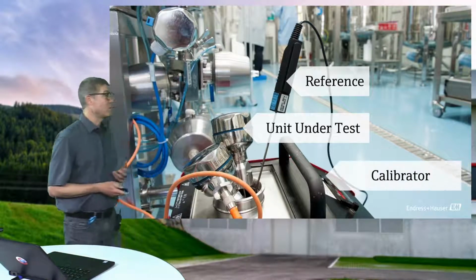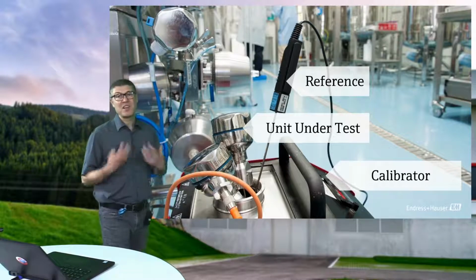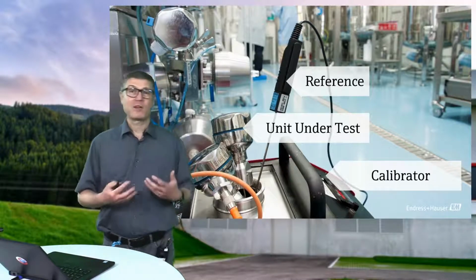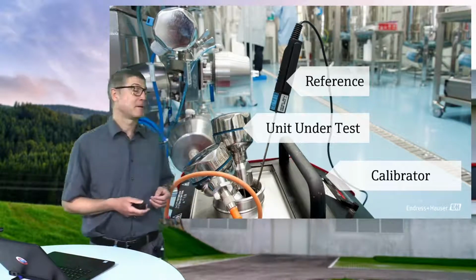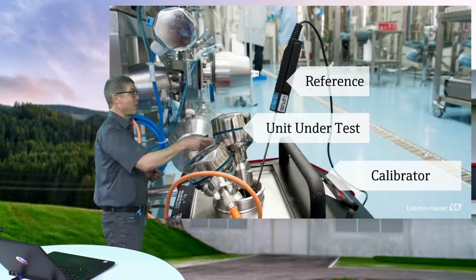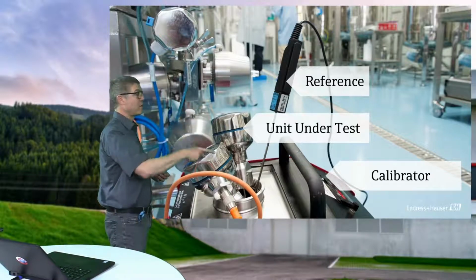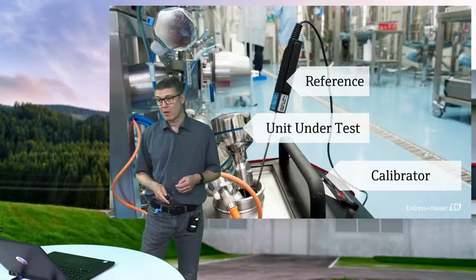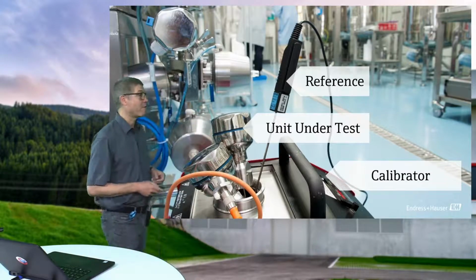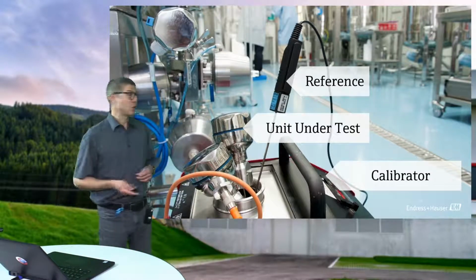And you need for sure your units under test, the thermometers you want to calibrate. And in this case, you need a calibrator, so you need a heat source. You need something which is heating up both, and then you compare the units under test with your reference thermometer. That is the basic principle of temperature calibration, which is usually performed.